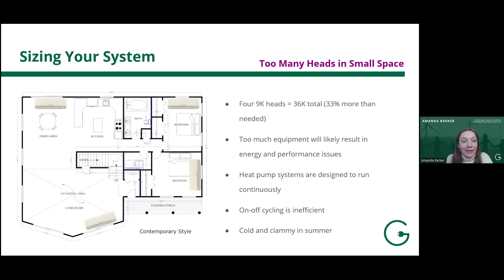The problem with this is that heat pump systems are designed to run continuously, not on and off. And so this system would be very inefficient. In the summer, you'd end up with cold and clammy air. The dehumidification cycle takes longer than the cooling cycle, so the air will not be dehumidified, but it will be cold. So too many heads in a small space will be not only more expensive because you're paying for more equipment than you need, but it's also more expensive to operate, and the comfort level is not going to be there as well. So we definitely recommend avoiding oversizing and putting a head in every room in a layout like this.